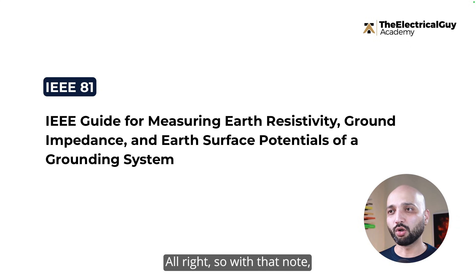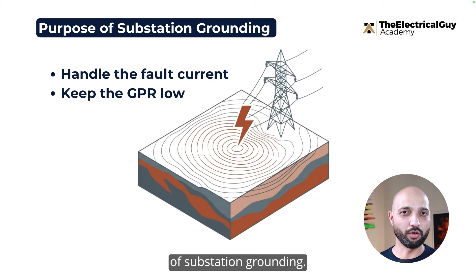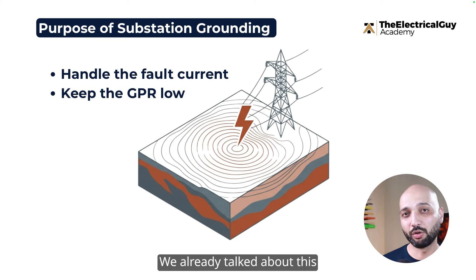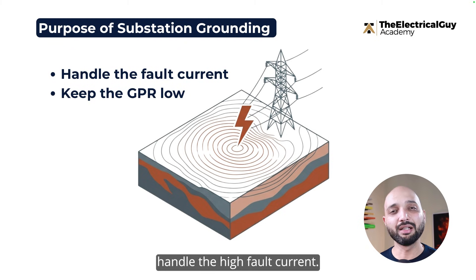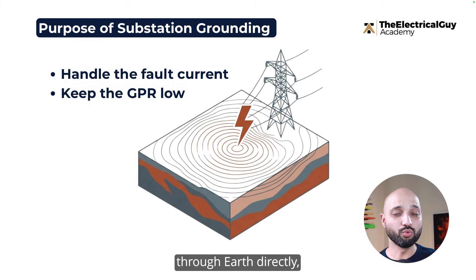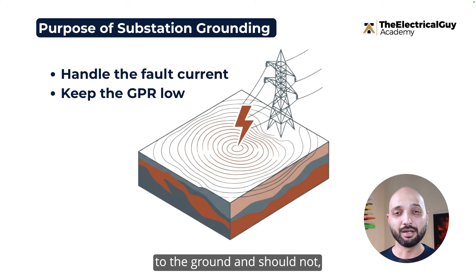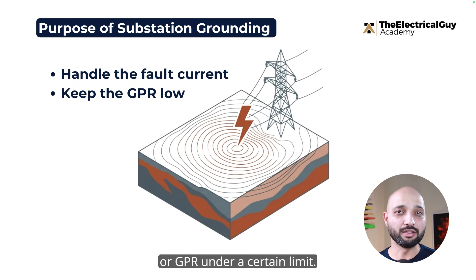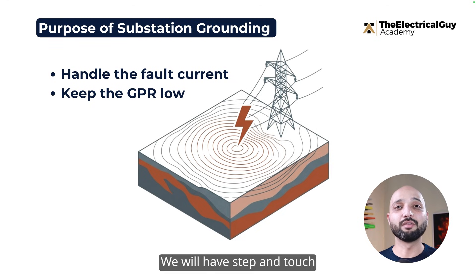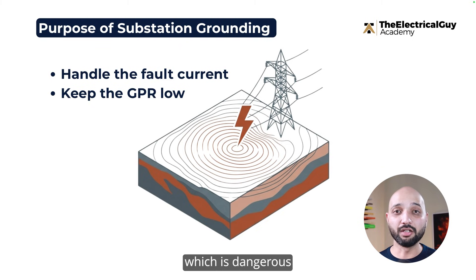Let's first understand the purpose of substation grounding. The first and most important purpose is that it should handle high fault current. When a ground fault occurs, it should go through the earth directly, and even when lightning happens it should go directly to the ground and should not enter any living being.